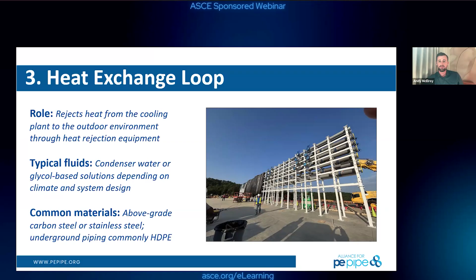High purity water is not necessarily a requirement on the data centers. On the chip fab side, it absolutely is—there's high purity polyethylene and then PVDF that are necessary in the chip manufacturing process. What I would differentiate though is we are seeing fusible on the secondary loop where the liquid is going directly to the chip. It's not necessarily high purity, but they need cleanliness because they can't have corrosion and scaling getting into the capillaries at the cold plates.